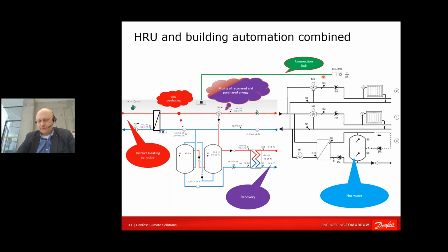When we need something, for example domestic hot water, and the temperature in the tanks is not high enough, we send a signal from the heat recovery to the cooling rack: please switch on your heat pump more, make us more energy. If that is not working, then we call for heat from the district heating utility or from the boiler plant, and we raise the temperature to the building. So we are capable of heating up domestic hot water, to process the anti-legionella feature, etc.